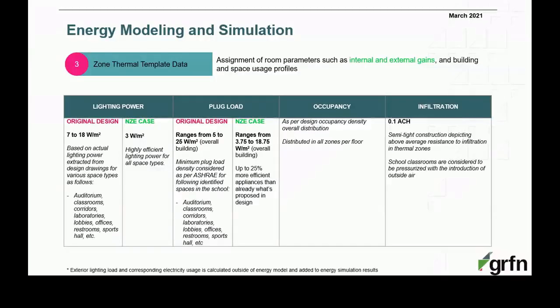Here we can see the loads, occupancy and infiltration. In terms of lighting, the original design had a lighting power density ranging between 7 and 18 watts per square meter. 18 basically, I think, was in the all-purpose room. Whereas with the net zero energy case, we were able to go down to 3 watts per square meter by using very high efficiency LED lights with power over Ethernet and a very advanced lighting control that takes into account daylighting, occupancy, and so on and so forth.